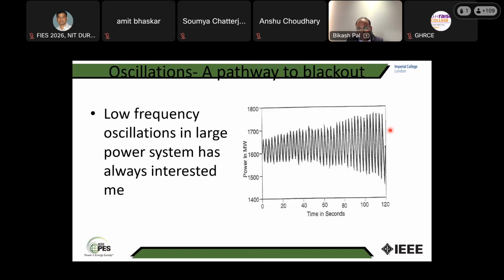And because this voltage would be dropping, there may be some distance relay in some line. It will see that, in that distance relay's zone 3, because of this high load, it would encroach, it would enter. And in that load encroachment, that distance relay will operate. So that line is out. Once that line is out, another resource is gone. So that way, one by one, you start actually losing your transmission circuits.